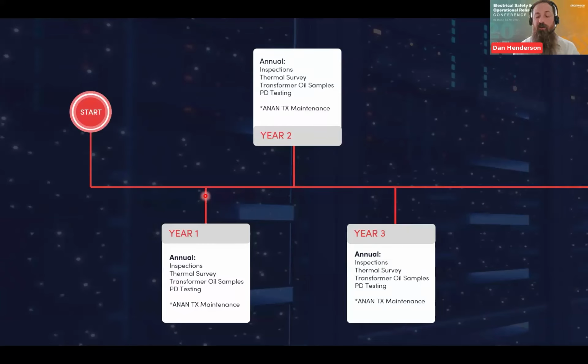Transformer oil samples. So again, next session, we're going to go right in depth with these ones. So we'll not go too far with that. But again, the transformer oil samples are so important because it tells you the transformer health. You know where you are with that asset and you can identify things early. Likewise with partial discharge testing, so that you can have an underlying, a small fault starting to develop that you can pick up with partial discharge testing. And if by doing that, just having that as part of your maintenance program, as part of your inspection regime, you can hopefully identify things early, which obviously hopefully don't result in an unplanned downtime or an arc flash if you're unlucky enough.